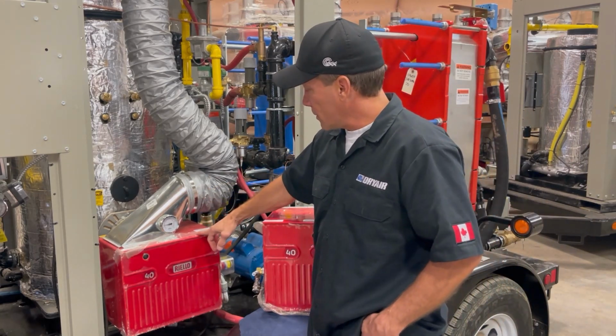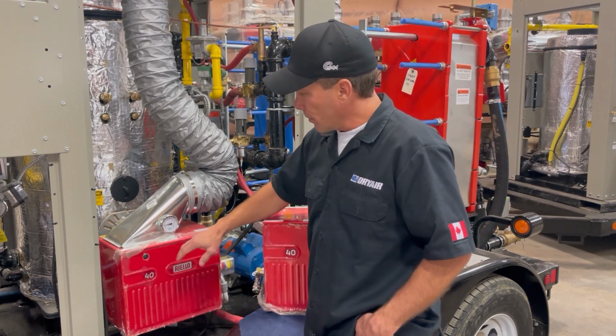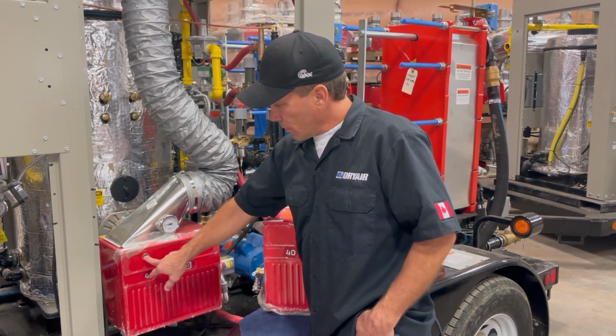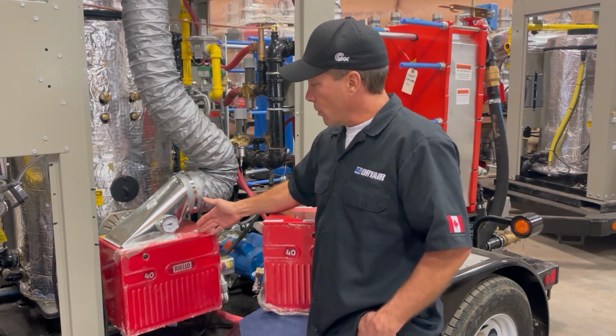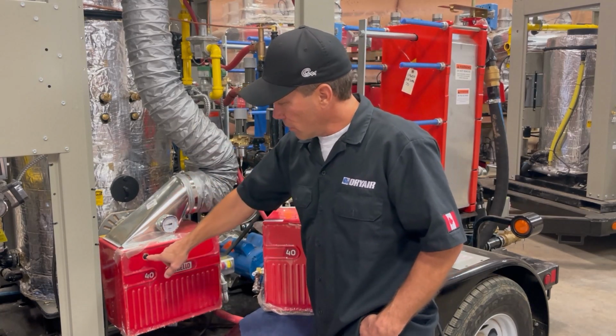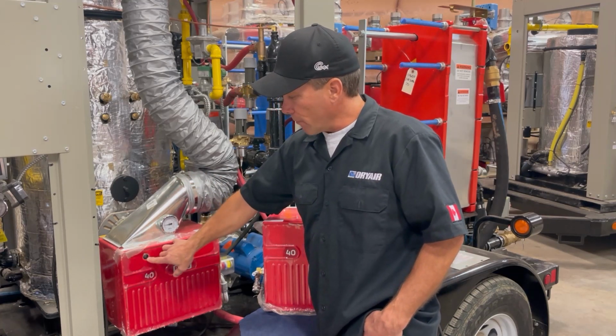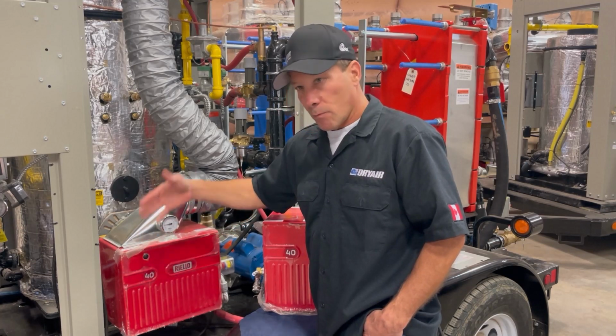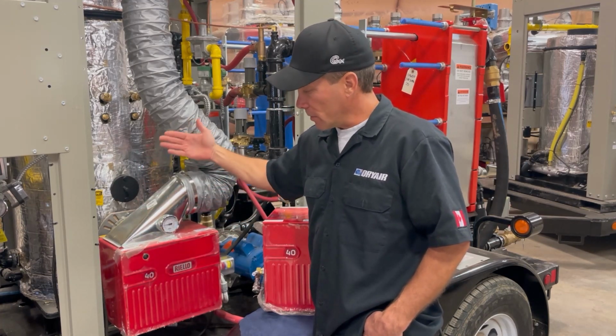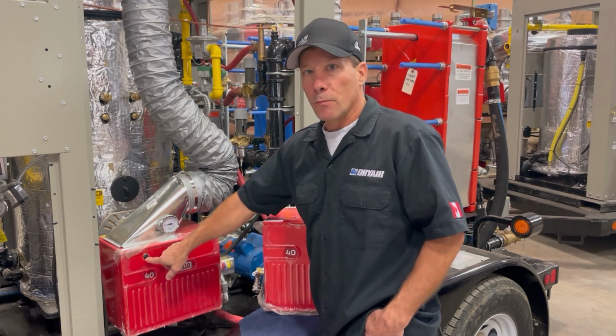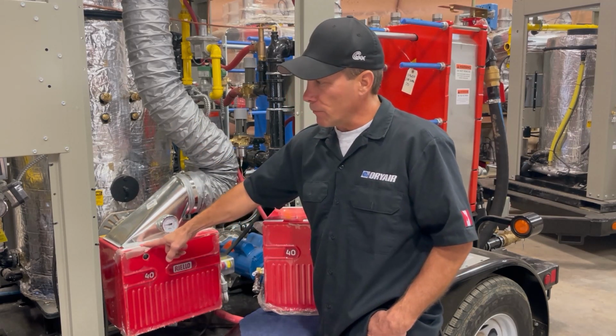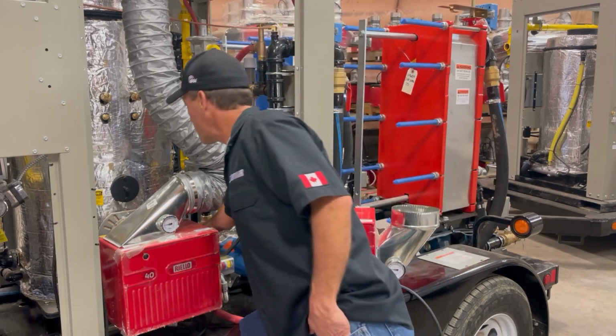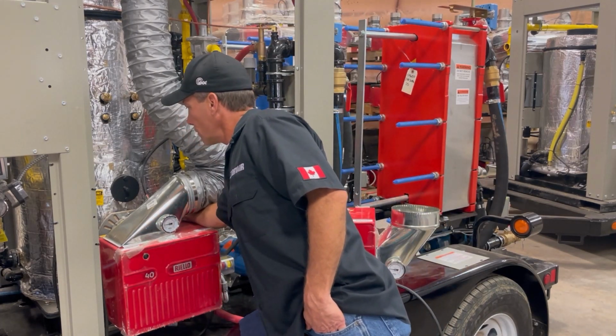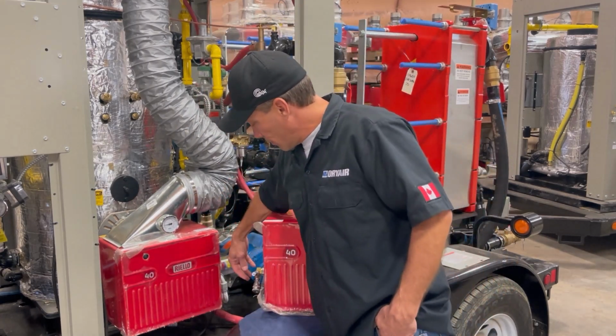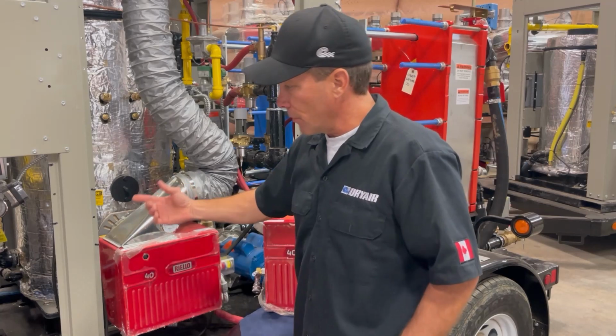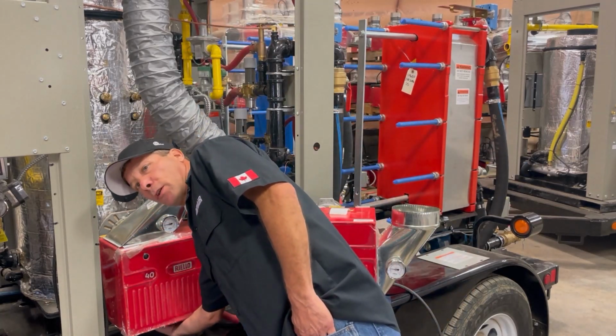As for the natural gas and propane burners, they're pretty much the same except for the reset button. So if this unit has air in the system and it shuts off, you can push this button in and it will give a flash code that will read 1, 2 flash, 3, 4 flash, 5, 6 flash, all the way up. By that you can look in the book and it'll tell you what needs to be fixed on the burner. This also plugs in back here. And for the diesel burners, your diesel comes in on the side, and you'll have a piece that plugs in underneath for your fuel.